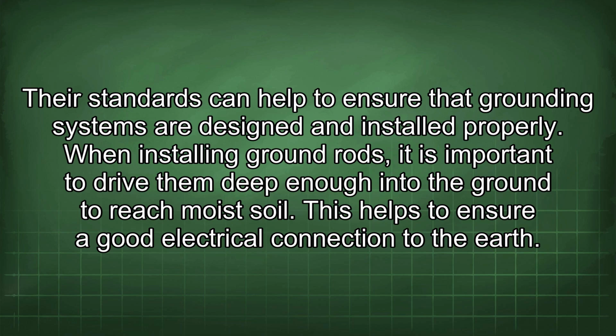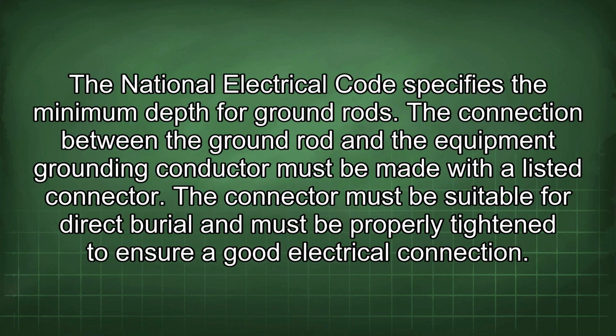When installing ground rods, it is important to drive them deep enough into the ground to reach moist soil. This helps to ensure a good electrical connection to the earth. The National Electrical Code specifies the minimum depth for ground rods. The connection between the ground rod and the equipment grounding conductor must be made with a listed connector. The connector must be suitable for direct burial and must be properly tightened to ensure a good electrical connection.